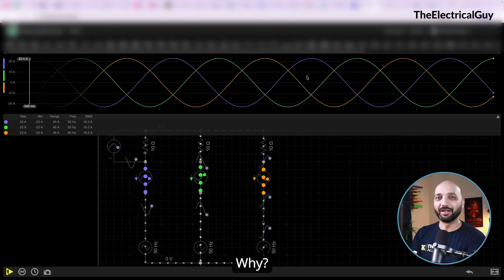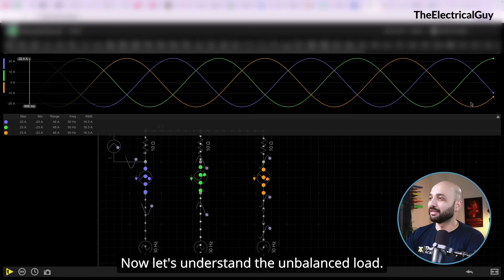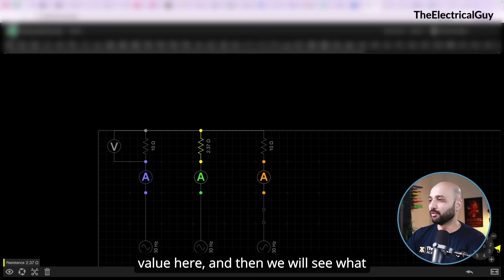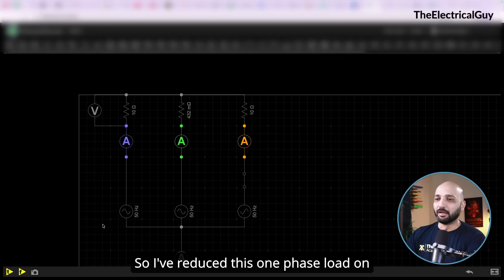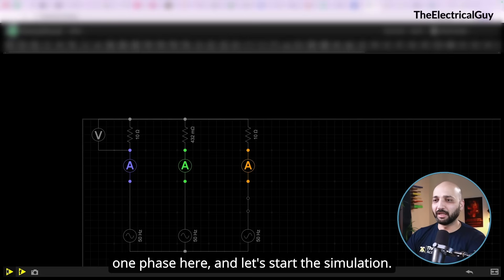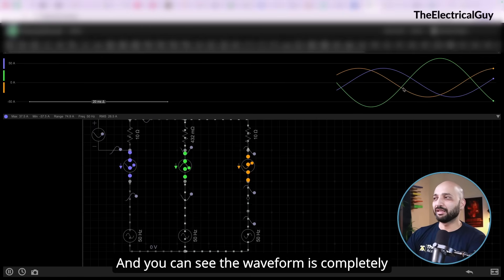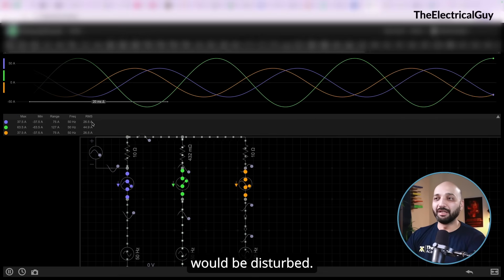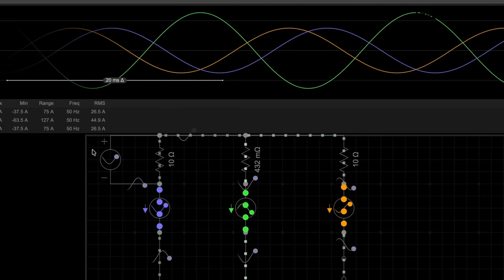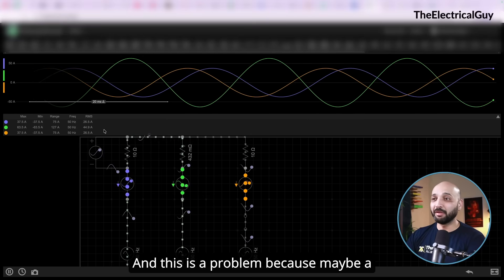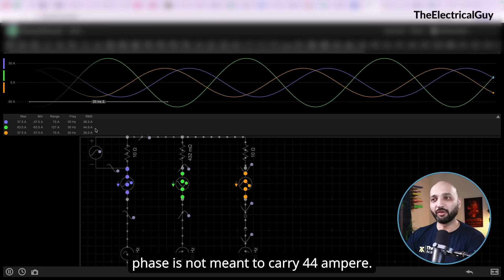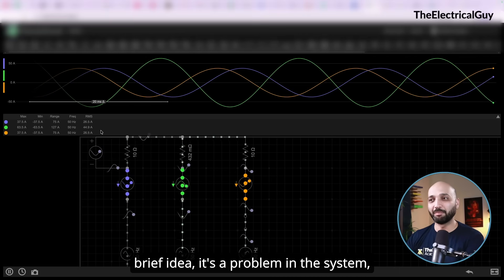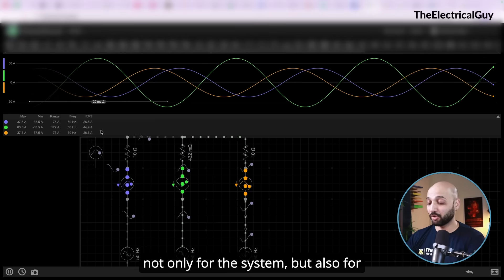Now let's look at the unbalanced load. I'm going to disturb this load by reducing the value on one phase and then see what happens. Starting the simulation, you can see the waveform is completely disturbed — not the same as before. The current flowing through each phase is now different. For example, the B phase is now carrying 44 amperes when it was only meant to carry 26 amperes. This will create overheating and is a problem not only for the system but also for the equipment.